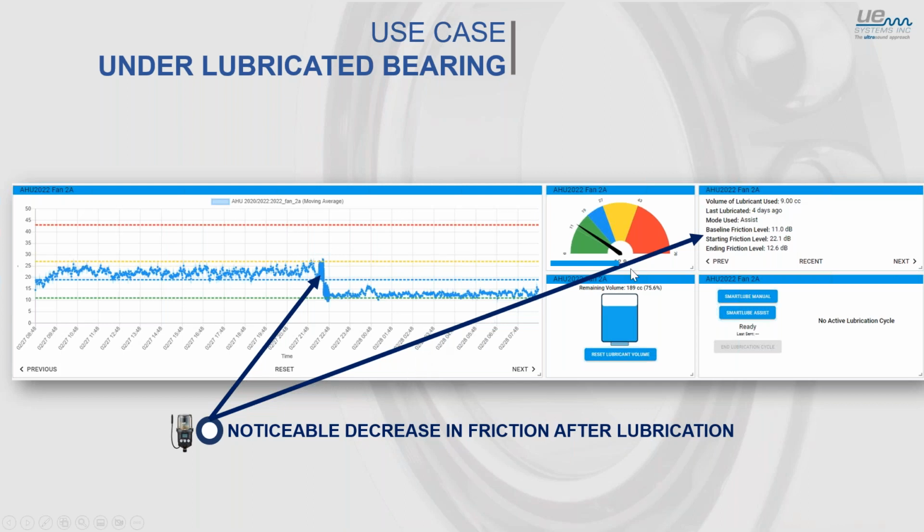And I'm going to say this slowly, because what came out of a year and a half, almost 2 years of having the OnTrak SmartLube system out is that most bearings require grease more frequently than even we thought, but the quantity is significantly less. And if you talk to any lubrication people out there, they like that, because why? It's constantly refreshing the grease, constantly moving that grease. So grease isn't sitting there in a single point lubricator, starting to separate from the oil, from the soap, from the thickener. It's constantly pushing it through, but only when it needs it. So this phenomenon that we saw was really welcomed by the lubrication community.